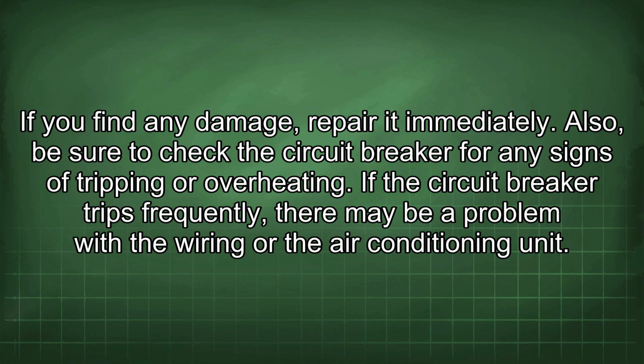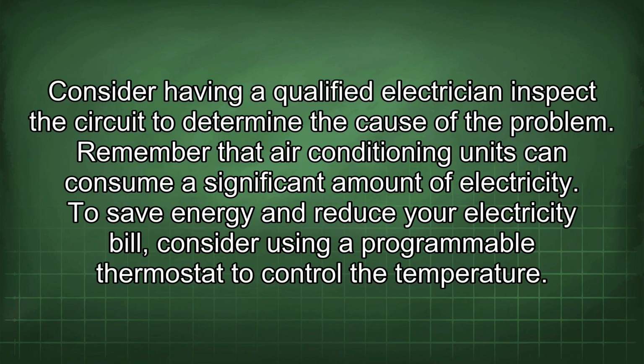Also, be sure to check the circuit breaker for any signs of tripping or overheating. If the circuit breaker trips frequently, there may be a problem with the wiring or the air conditioning unit. Consider having a qualified electrician inspect the circuit to determine the cause of the problem. Remember that air conditioning units can consume a significant amount of electricity.